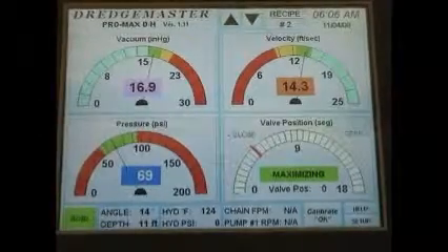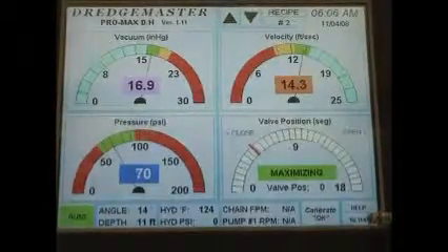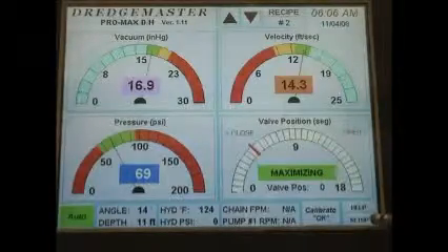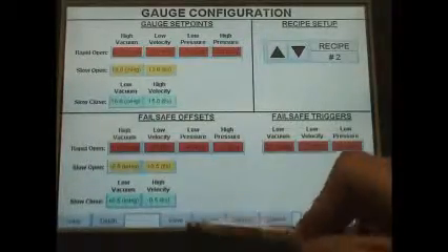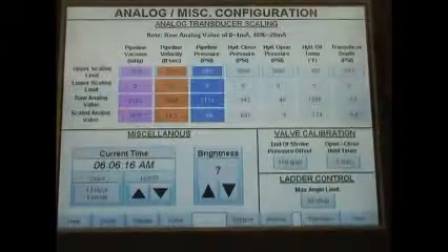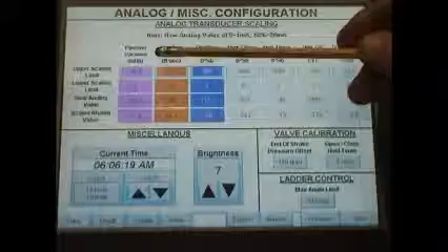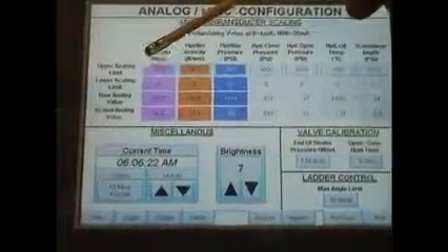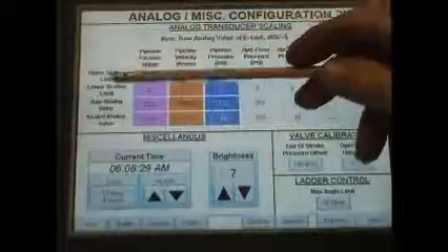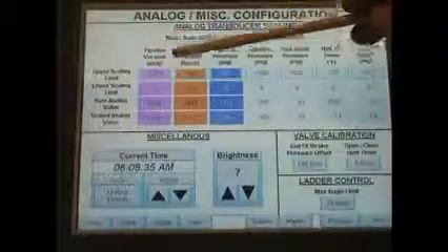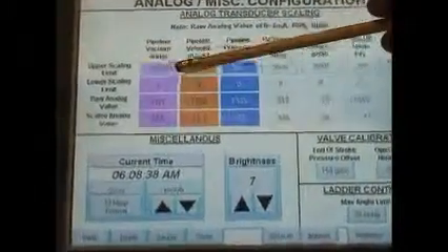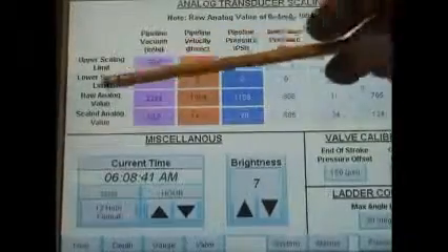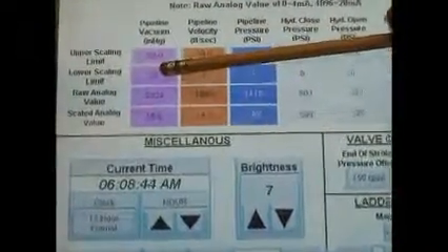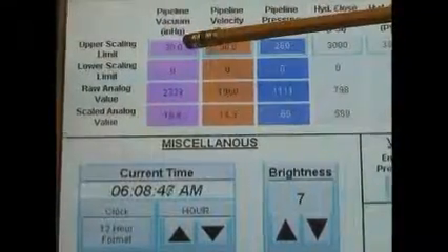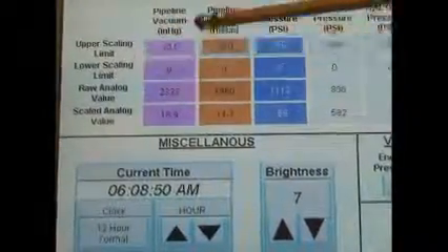The Dredgemaster has some setup parameters for each one of these transducers. To get to those, you just touch the setup button and go to the analog tab at the bottom. Select analog. Here we're looking at the pipeline vacuum gauge transducer. All of these set points, which is our upper scale limit, tells us that the vacuum transducer has the capabilities of going to 30 inches of mercury, and the lower scaling is 0. So basically this transducer goes from 0 to 30 inches of mercury is the setting of this vacuum transducer.